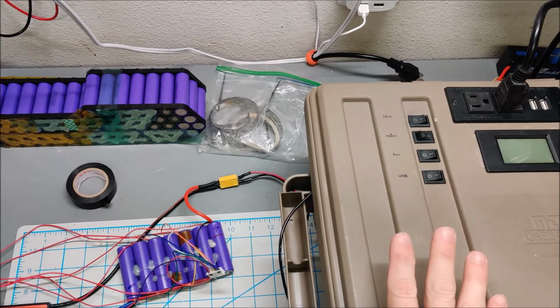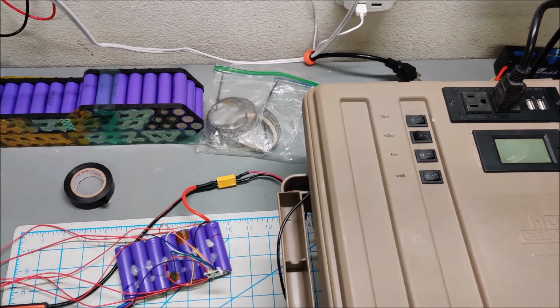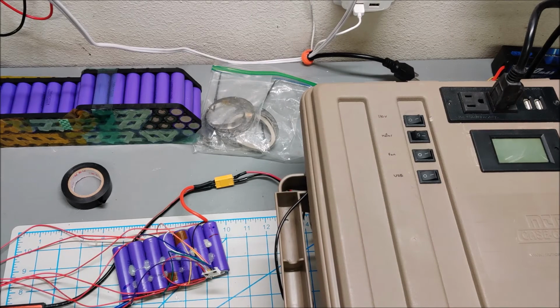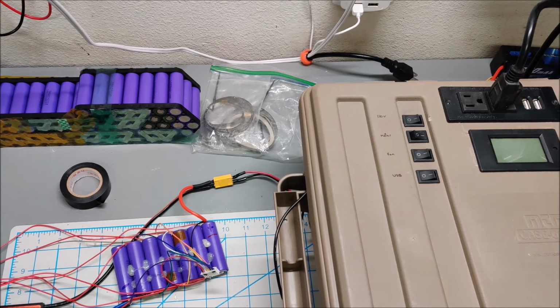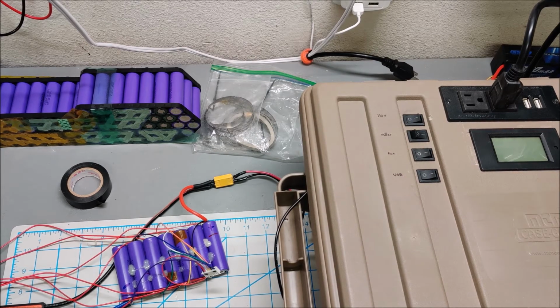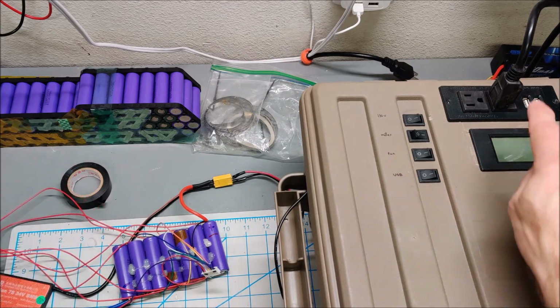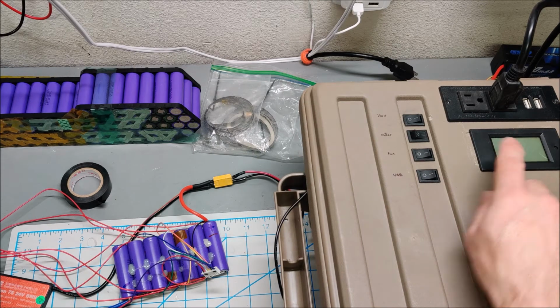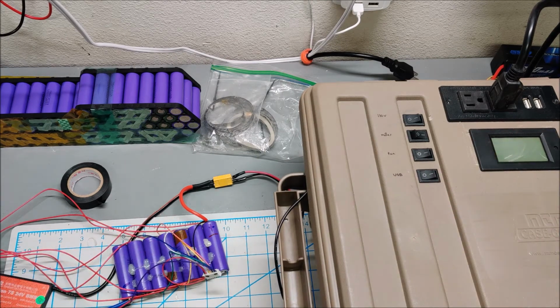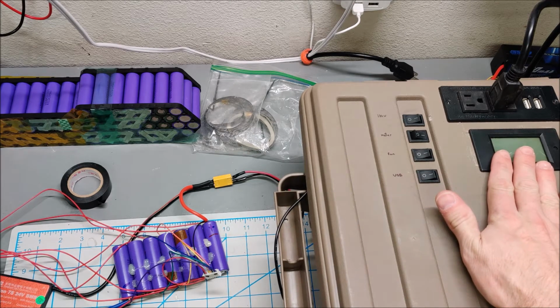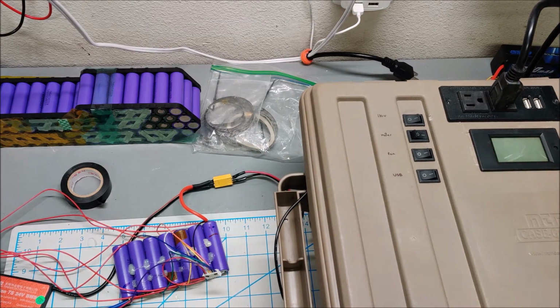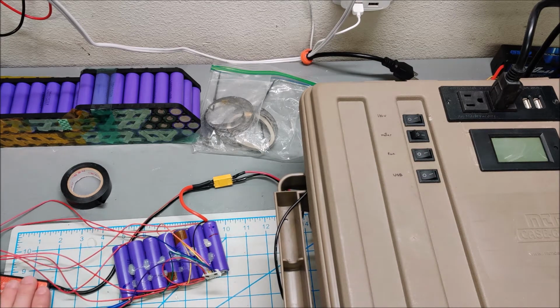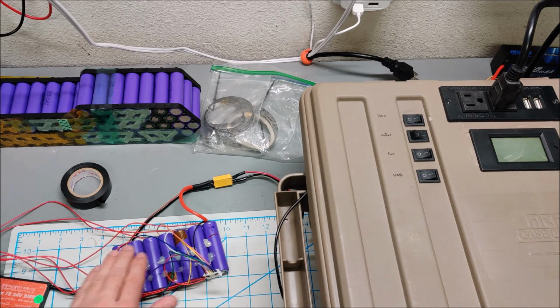Okay, so the solar generator has shut off. We don't know if the BMS killed it or the inverter did. We need to check some voltages, but it's probably the BMS, because I noticed the meter is off. If the battery was still on but the inverter had just shut off, the meter would probably still be running. The fact that it's off probably means the BMS killed everything, which is good. Let's check the voltage of this pack and see how low we got.